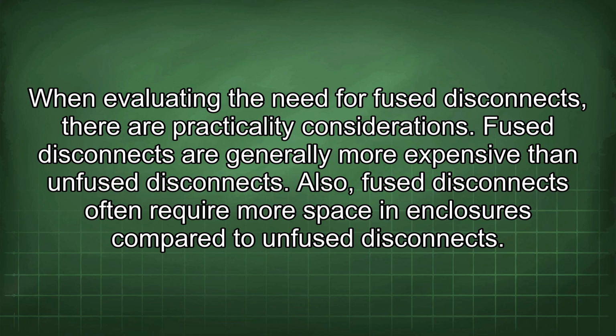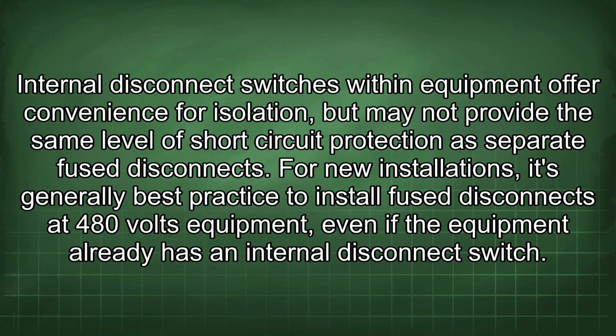Fused disconnects are generally more expensive than unfused disconnects. Also, fused disconnects often require more space in enclosures compared to unfused disconnects. Internal disconnect switches within equipment offer convenience for isolation, but may not provide the same level of short-circuit protection as separate fused disconnects. For new installations, it's generally best practice to install fused disconnects at 480 volts equipment, even if the equipment already has an internal disconnect switch.